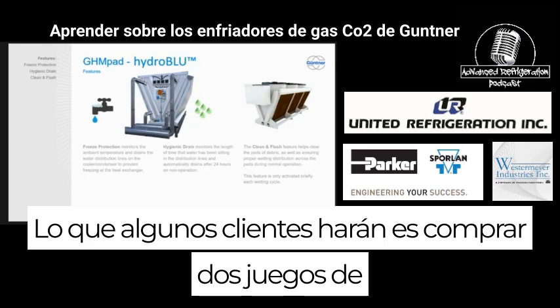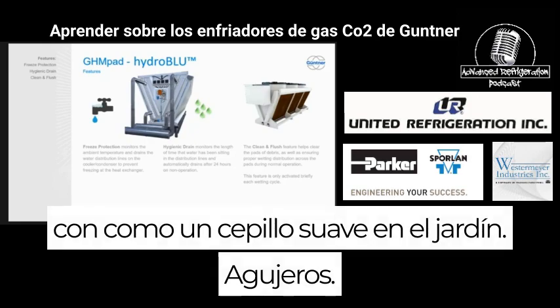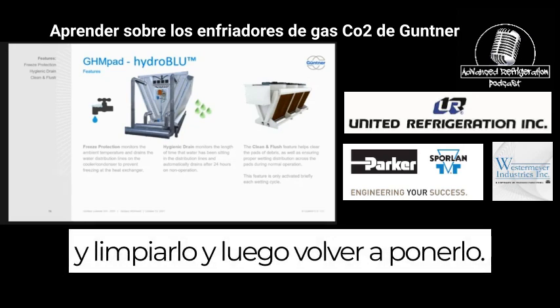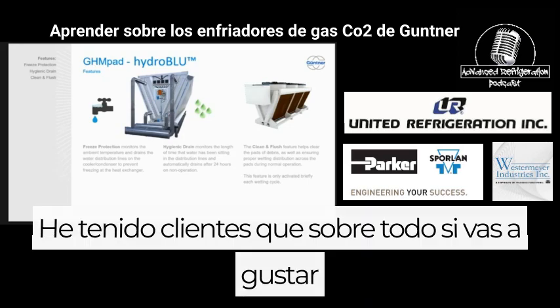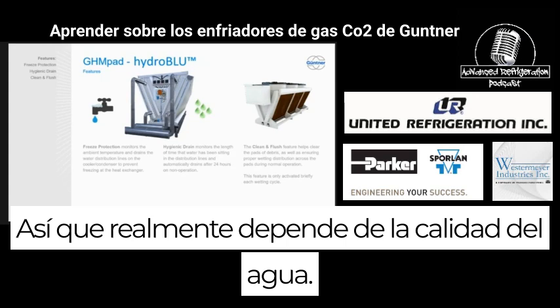What some customers will do is buy two sets of pads. They take one set off and clean it with a soft brush and a garden hose. Don't use a pressure washer on these, but some mild soap and clean it off and then put it back on. I've had customers, especially in Arizona where they have really, really hard water, who have had to replace it every 6 months. So it really depends on the water quality.